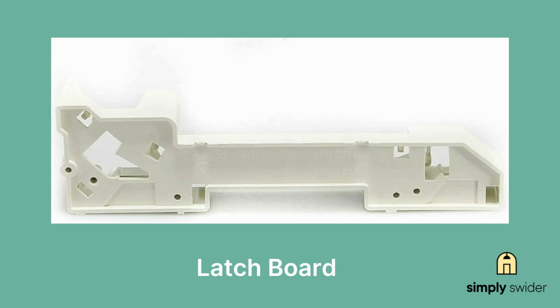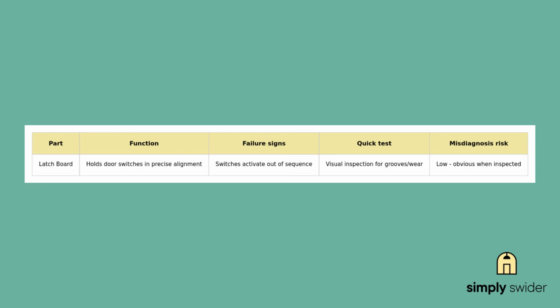Speaking of the latch board, that plastic frame that holds all the switches runs about 20 to 50 bucks. It's not a hard job, but you've got to be careful about the alignment. Those switches have to activate in the exact right sequence or you're back to tripping breakers. I had this customer who tried to save money by just replacing the switch, but the latch board was so worn that the new switch lasted exactly 3 days. Don't be that guy. If you see grooves or wear on the plastic ramps, replace the whole assembly.